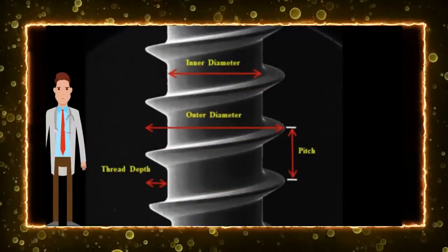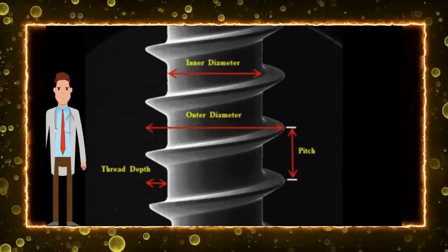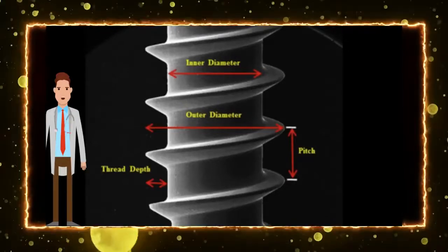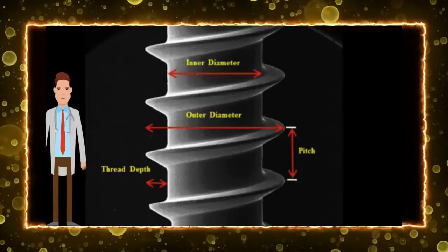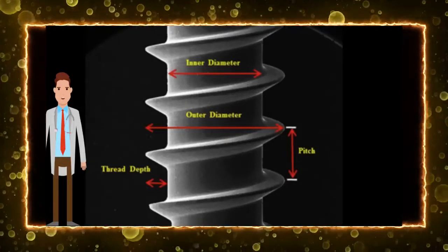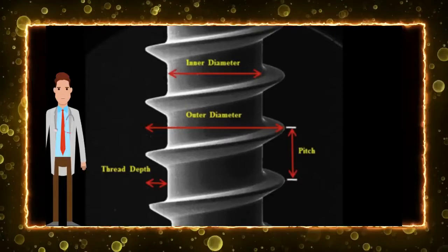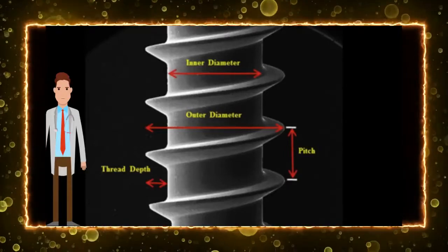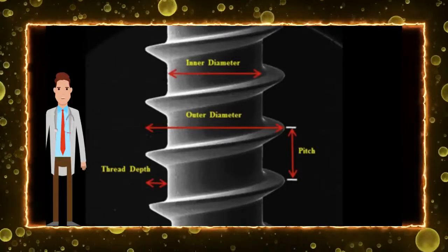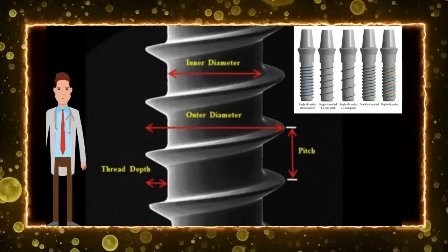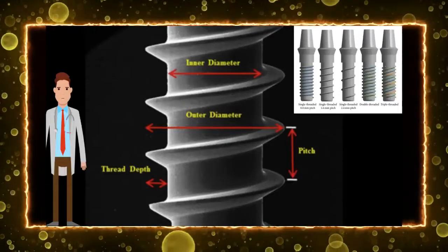You have thread shape. The type of force applied at the implant-bone interface may influence the degree and strength of osseointegration. The type of force that is generated depends on the shape of the implant thread. Hence, an ideal implant thread design should provide a balance between compressive and tensile forces while minimizing shear force generated. I chose the square thread design because it has the least shear force generated and it has a balance between compressive and tensile forces. Thread depth and thread width.